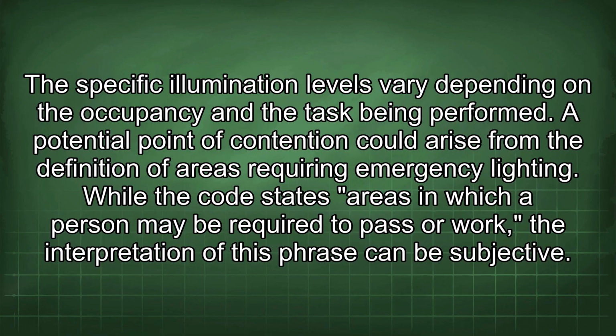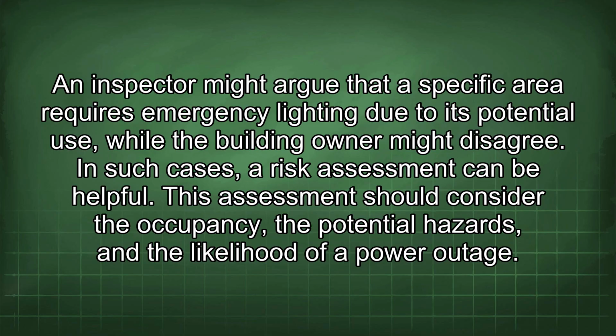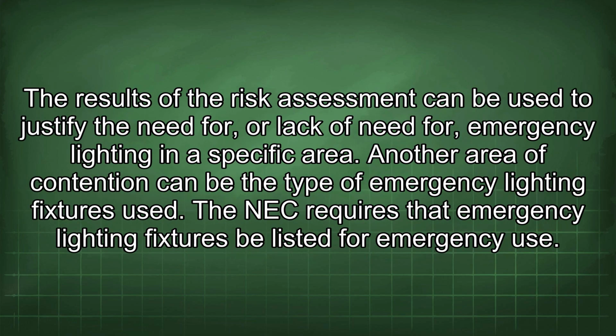A potential point of contention could arise from the definition of areas requiring emergency lighting. While the code states areas in which a person may be required to pass or work, the interpretation of this phrase can be subjective. An inspector might argue that a specific area requires emergency lighting due to its potential use, while the building owner might disagree. In such cases, a risk assessment can be helpful. This assessment should consider the occupancy, the potential hazards, and the likelihood of a power outage. The results of the risk assessment can be used to justify the need for, or lack of need for, emergency lighting in a specific area.